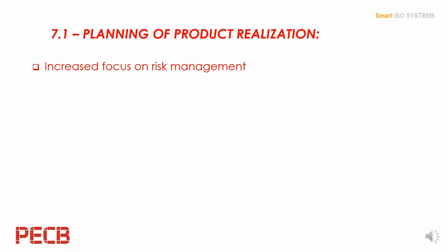One of the biggest changes to section 7.1 is the requirement to document how the risk management activities are being handled for product planning. The draft guidance highlights several areas where risk management should be incorporated: verification, validation, revalidation, monitoring, testing, and traceability. You will need to conduct an assessment considering the risks as you're planning for those activities and that the process has been documented. A note was also added requesting organisations to look at IEC 62304, which is guidance related to software lifecycle processes. If your device incorporates software, then the guide requires you to look at the different life cycles of that software, so you're planning ahead of time for future changes.